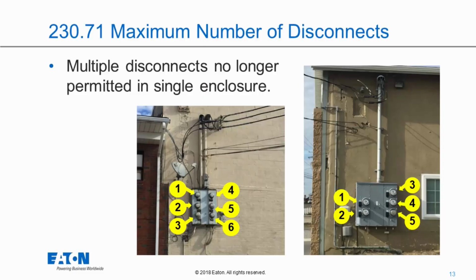And really, if you look in UL 67, there's really no way, from a UL perspective, to have guidance on how to compartmentalize those main tenant devices. So the rule for now is, when it comes to meter centers, you really just need to have a single main for those meter centers. You cannot really purchase them with the compartmentalized construction.